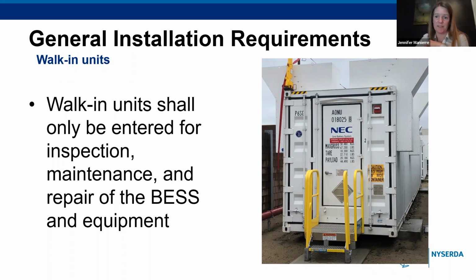One of the reasons that is good is because if there is an incident and emergency responders show up, they can be fairly certain that there's not going to be people inside of these shipping containers, these systems, because they're only ever going to be accessed for maintenance. Otherwise, they're locked off. So we advise, unless you have a good reason to think that someone is in there, just stay out. Don't want a repeat of that Arizona incident that I talked about earlier.